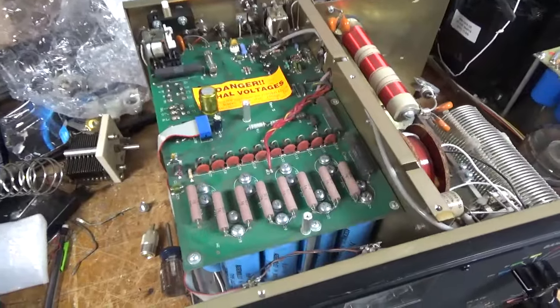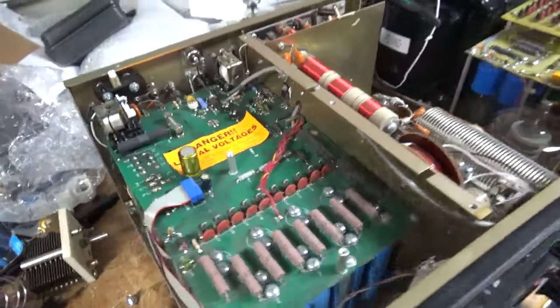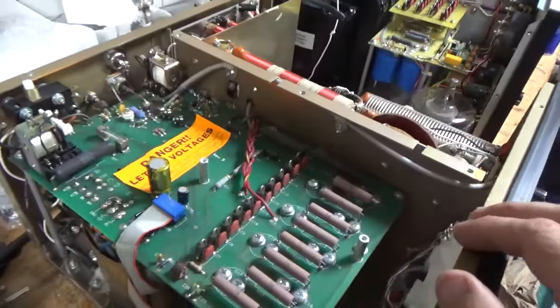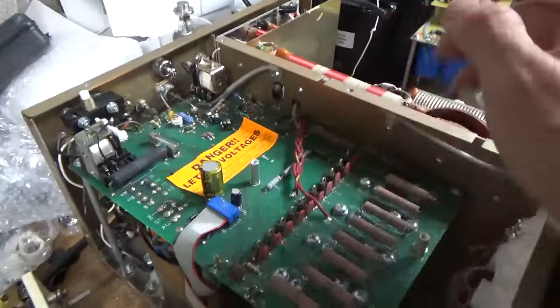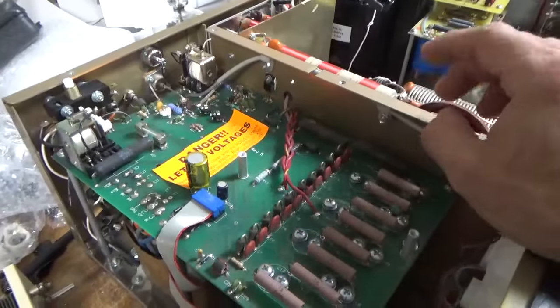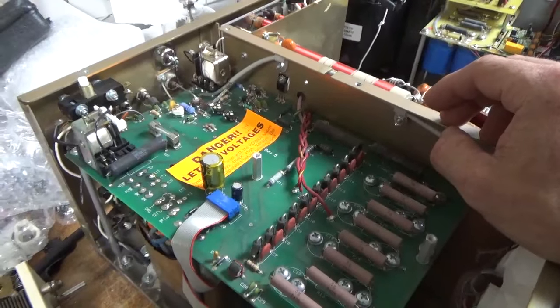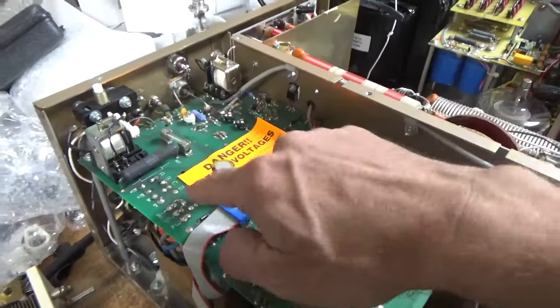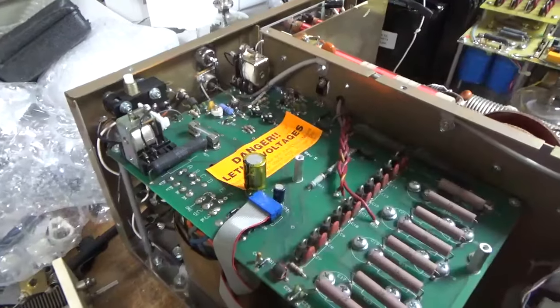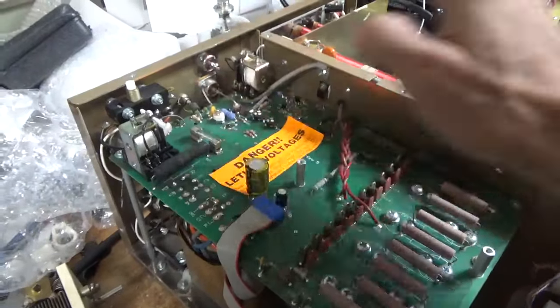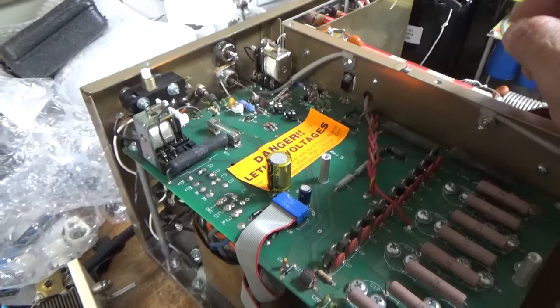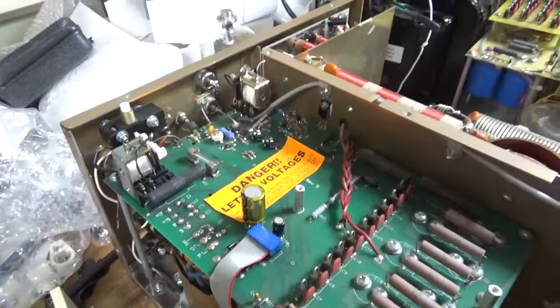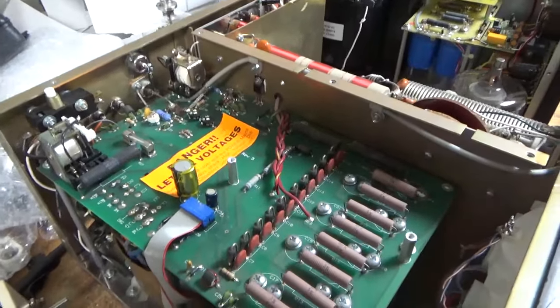Okay, I forgot to add that it's wired for 240. That's why it needs the 10 amp fuses. And I'm going to ask him what he has for nominal line voltage. If it's above 240, closer to 245, I will adjust the buck boost taps here. Right now it's on the 241. I'll put it on the 245. All right, so I will see you guys soon. Stay tuned.